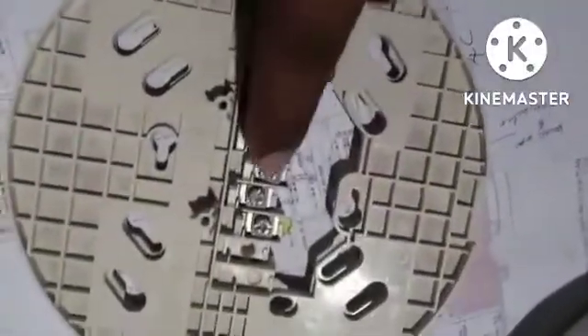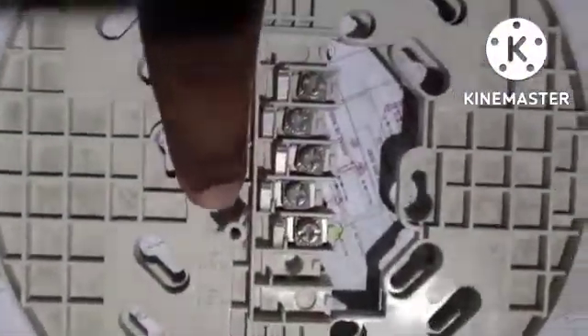You can see here where to connect the cables. The first two terminals are not used. This one labeled RI is for the remote indicator. EXT means auxiliary power — we need an additional auxiliary power cable for the sounder base.